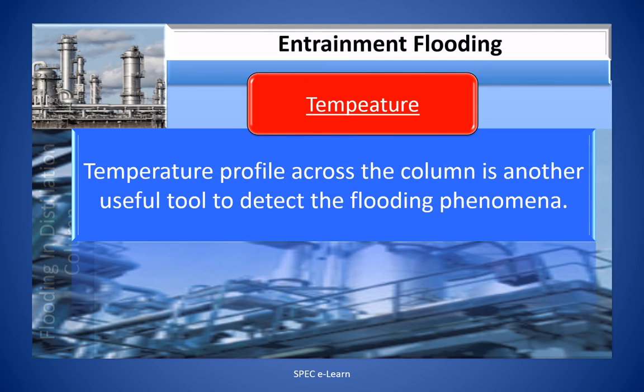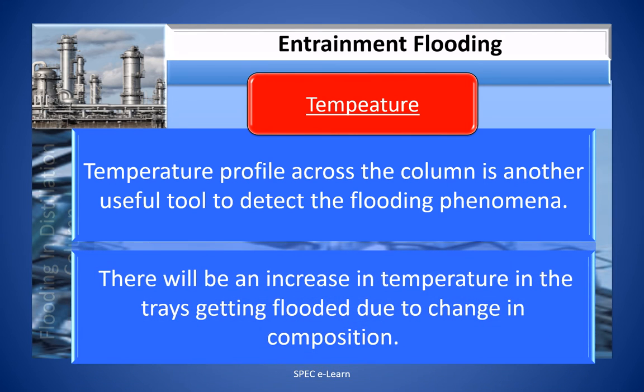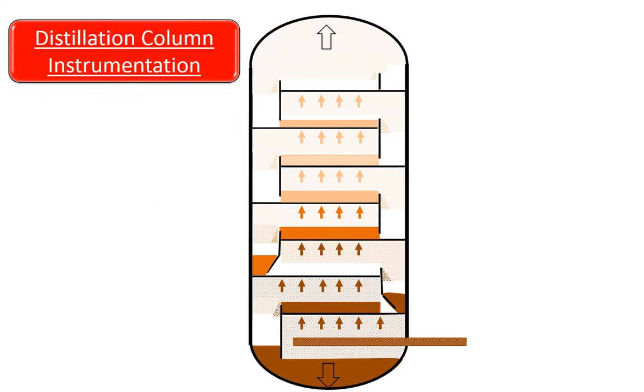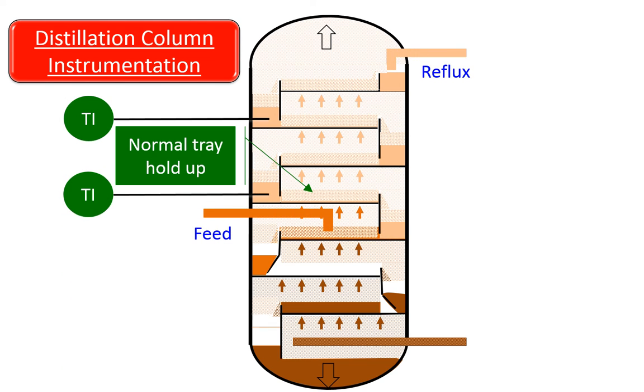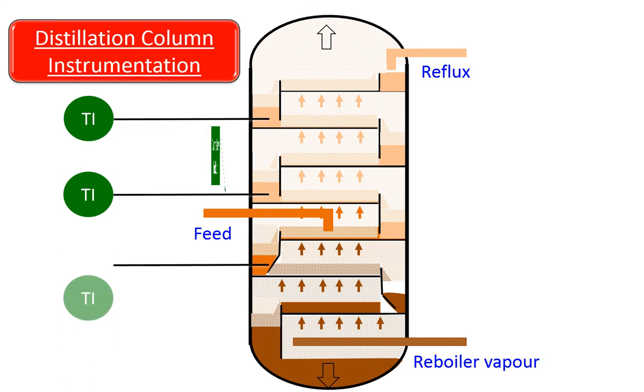Monitoring tray temperature. Temperature profile across the column is another useful tool to detect the flooding phenomenon. There will be increasing temperature in the trays getting flooded due to changes in composition. This figure shows the temperature measuring instruments installed on the trays; the increase in temperature can be monitored as a trend in the flooded zone.